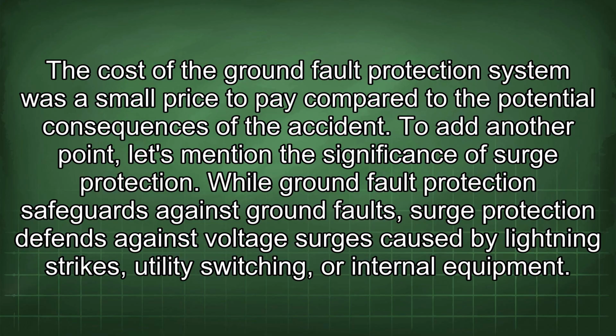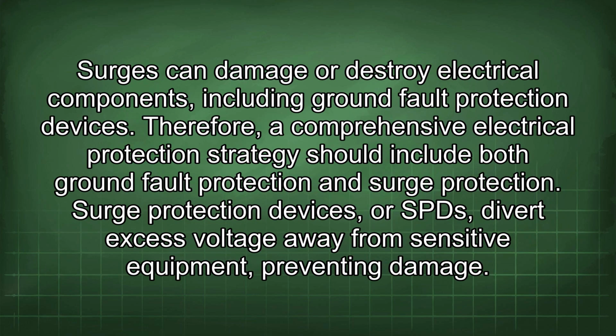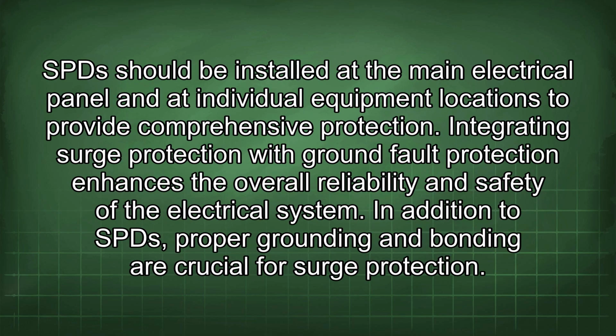While ground fault protection safeguards against ground faults, surge protection defends against voltage surges caused by lightning strikes, utility switching, or internal equipment. Surges can damage or destroy electrical components, including ground fault protection devices. Therefore, a comprehensive electrical protection strategy should include both ground fault protection and surge protection. Surge protection devices, or SPDs, divert excess voltage away from sensitive equipment, preventing damage. SPDs should be installed at the main electrical panel and at individual equipment locations to provide comprehensive protection. Integrating surge protection with ground fault protection enhances the overall reliability and safety of the electrical system.